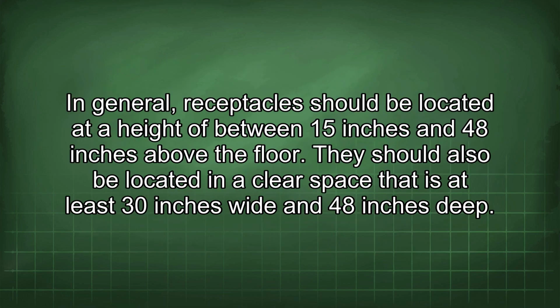In general, receptacles should be located at a height of between 15 inches and 48 inches above the floor. They should also be located in a clear space that is at least 30 inches wide and 48 inches deep.